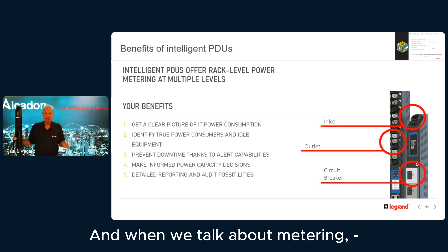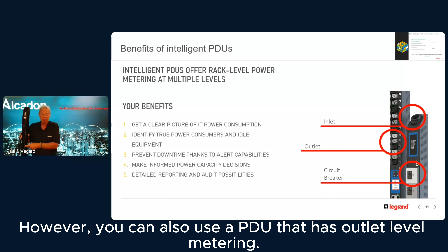When you talk about intelligent PDUs, it's most of the time metering. And when we talk about metering, there are a few levels where you can measure the power consumption. First of all, you can measure the power consumption on the inlet level. That means that you can see the total power consumption of all connected computers. This gives you basic information about what's happening at the rack level. However, you can also use a PDU that has outlet level metering. And our recommendation is that you use outlet metering because then you can see the power consumption of every server that is connected. And this gives you a lot of detailed information on what the servers are doing.